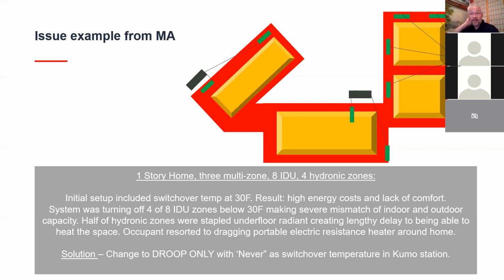No harm, no foul. The system was immaculately well installed. There's really no problems with the installation whatsoever. But inside of the controls, they followed guidance and set a switchover temperature at 30 degrees. So anytime it would drop below 30 degrees, into the 20s, like it does even in Massachusetts, suddenly 4 of the zones would shut off. These correspond to 4 parts of the house shown in gold. This house was actually 3 structures connected with indoor breezeways, combined totaling something like 3,400 square feet. The multi-zones correspond to each one of those 3 boxes, and the hydronic zones fed off an oil boiler corresponded to each one of those 3 structures.